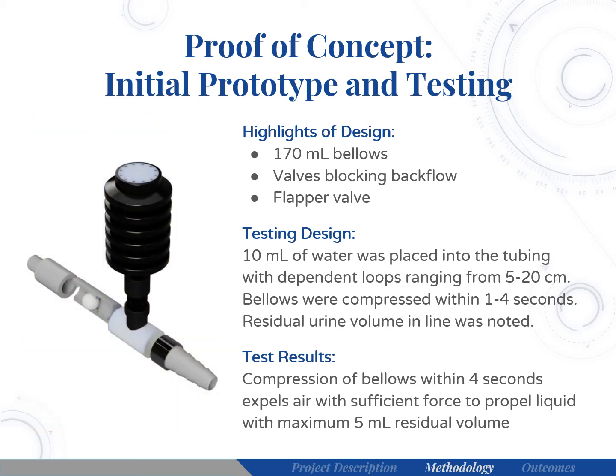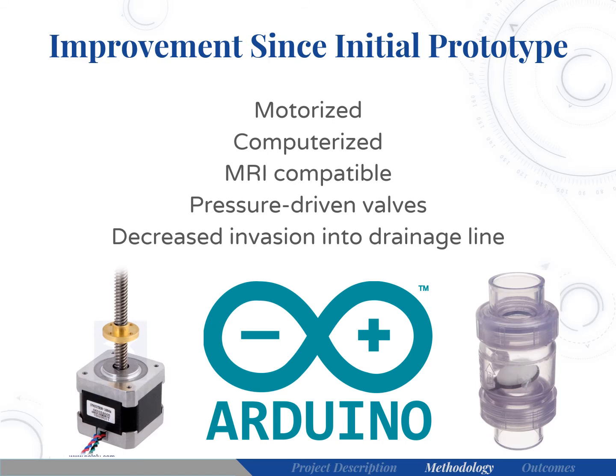The results demonstrated that compression of the bellows within 4 seconds produced enough pressure to propel the water with maximum 5 milliliters residual urine. This helped confirm that the general idea of the design was sufficient and something we could improve on. From the initial prototype, we have made some improvements. We incorporated a motor and a computer-driven system, transitioned to a removable device to facilitate MRI compatibility, instigated pressure-driven valves, and decreased drainage line invasion.